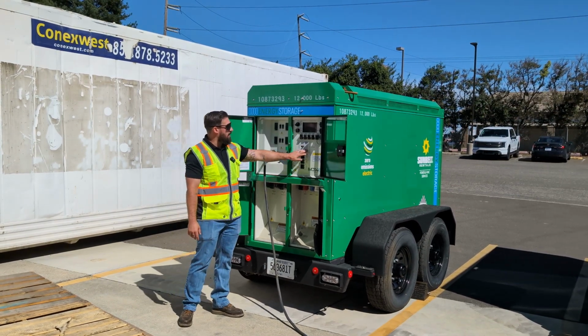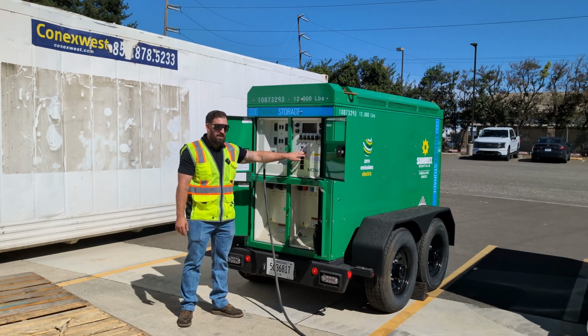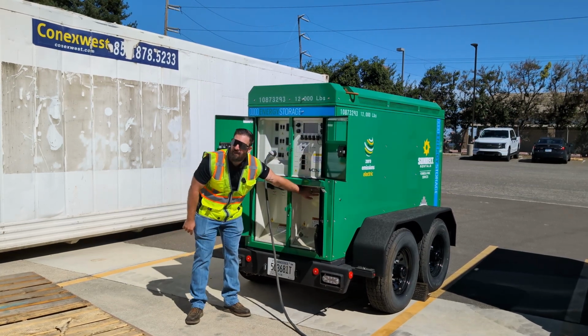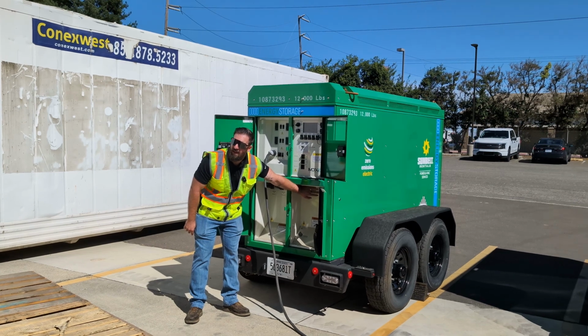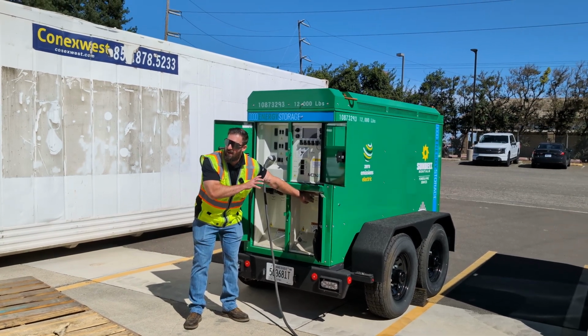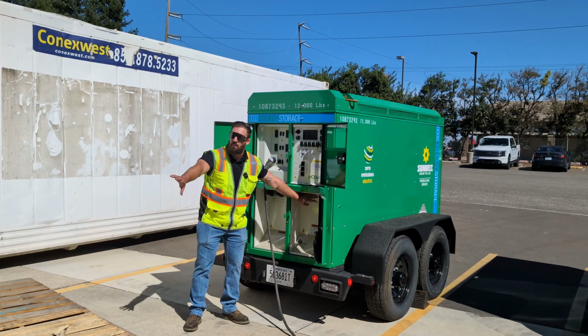From here, we have our main circuit breaker that always needs to be on when we are powering something. At the bottom here, we have our inlet 400 amp cams that can be connected into, so if we want to run straight cabling to a panel, we can connect through the cam lock.